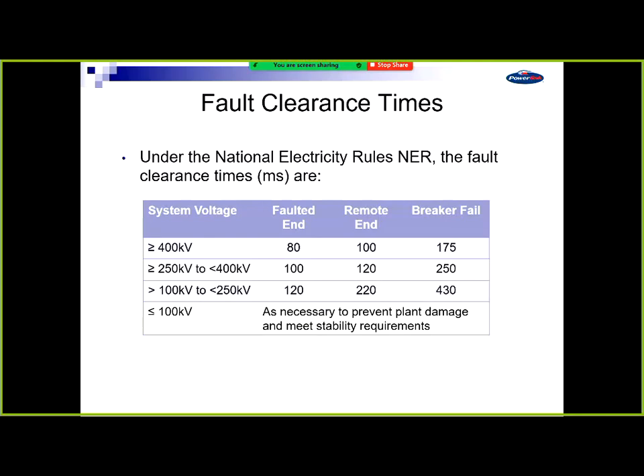Now this is the National Electricity Rules, the fault clearance times. Powerlink's network operates at 110, 132, 275 and 330 kV. So you can see that the times to clear faults are about 100, 120 milliseconds. That's quite high speed to detect and clear correctly as well. So you don't want to be tripping spuriously, and you haven't got much time.